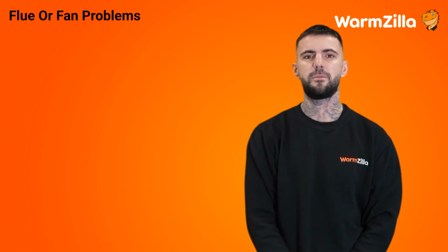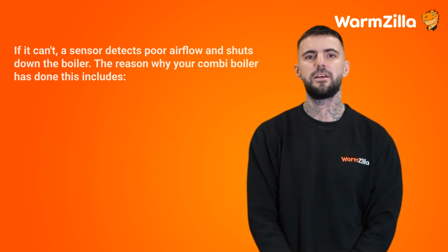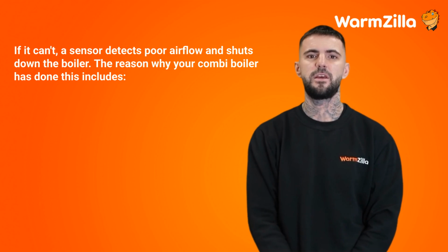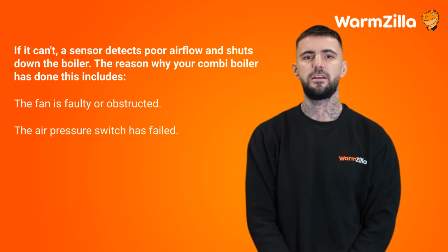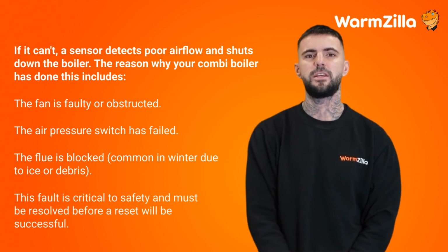Flue or fan problems. Your boiler uses a fan to expel dangerous combustion gases through the flue. If it can't, a sensor detects poor airflow and shuts down the boiler. The reason why your Combi boiler has done this includes the fan is faulty or obstructed, the air pressure switch has failed, the flue is blocked, common in winter due to ice or debris. This fault is critical to safety and must be resolved before a reset will be successful.